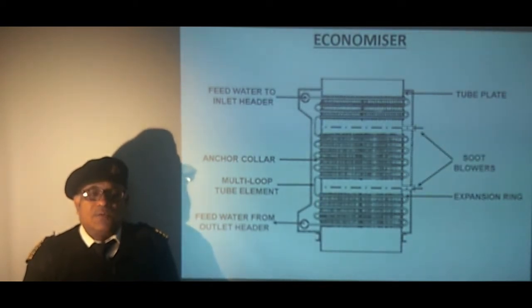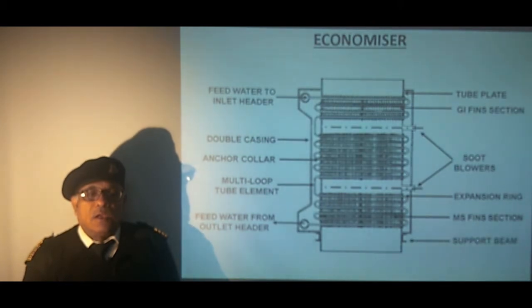We have the soot blowers for keeping the surfaces clean. We have mild steel fins in the lower part of the economizer. And we have galvanized iron fins in the upper part of the economizer where water temperature is low. We have the double casing. So the ends are not heated. We have the support beam on which the economizer is mounted.